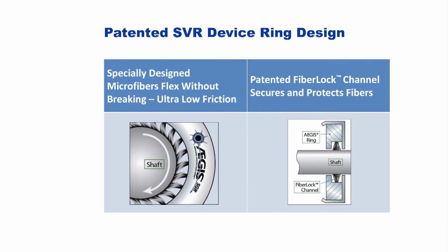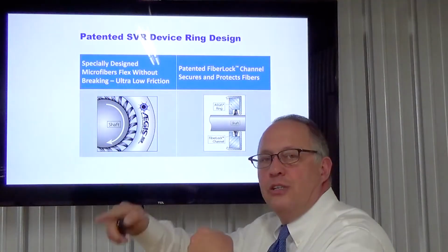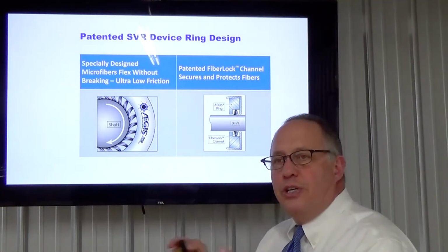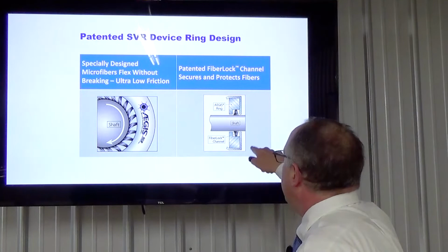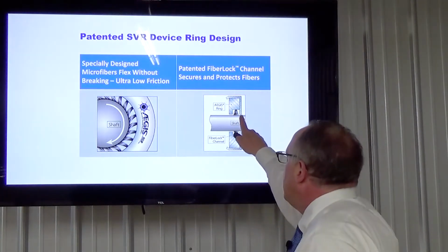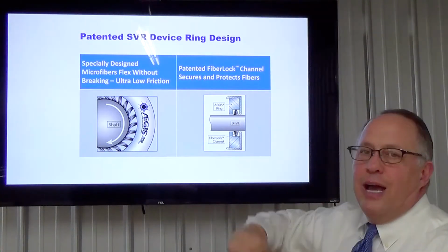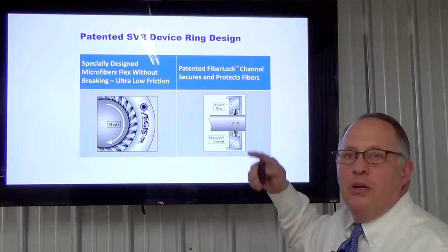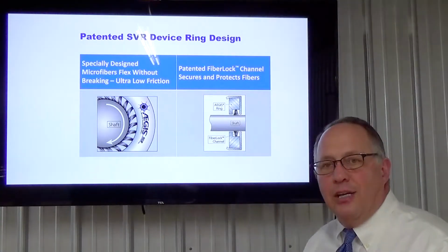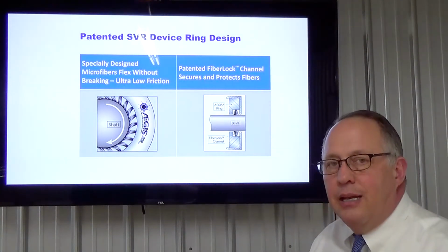The SVR device, there are patented devices that are out there. This is just showing up close the fibers around the shaft. It's completely around the shaft all the time. This channel comes up where the fibers provide the path to the channel of the ring, and the ring is attached to the frame of the motor, and then a path to ground.